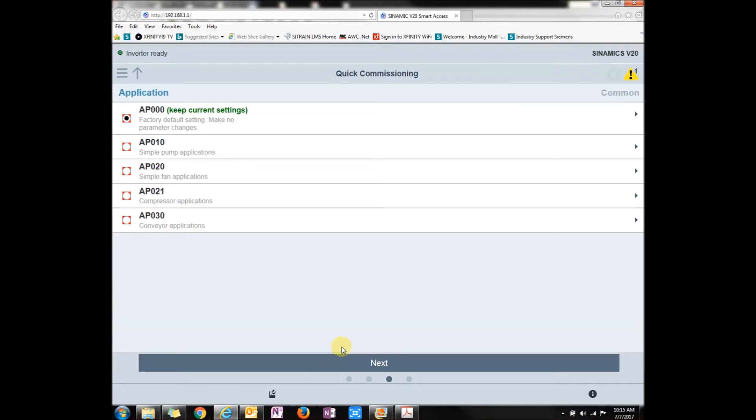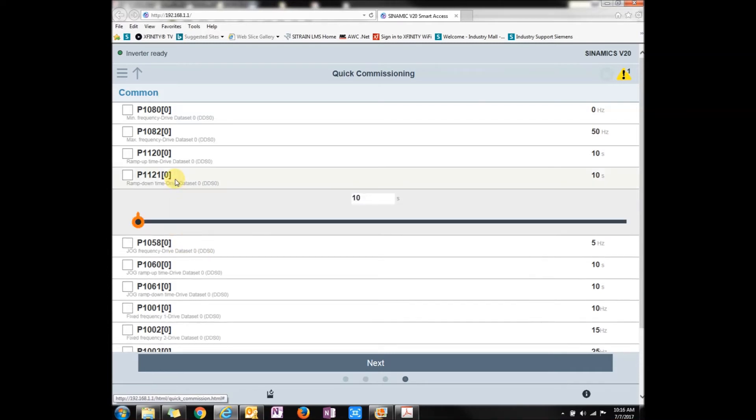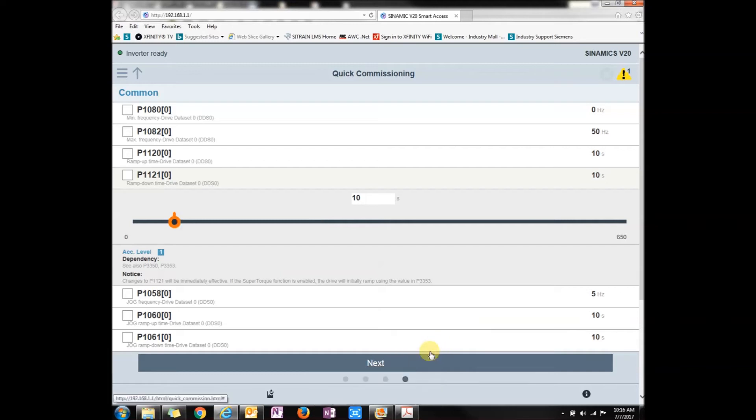Next would be your application macro. This is how you set it up for like a pump or a fan conveyor. Next would be how fast you're wanting this VFD to ramp up or ramp down. Let's mess with the ramp down time. You can click on it, and it kind of tells you what it's about. You can either scroll this over, which adds time to it, or you could physically click on the number itself, and then there's a little keyboard that shows up. Let's put it like 10 seconds, press down, and you're done.